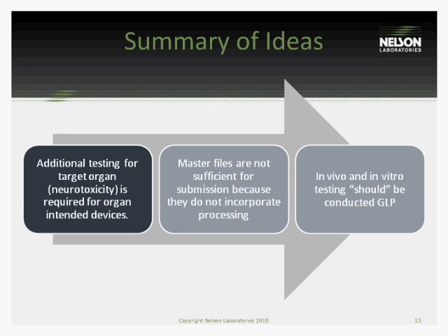Now, master files can help in a risk assessment. In fact, they help a lot in a risk assessment. But you cannot just submit master files and think you have a checkbox with your biocompatibility, because those master files may not have been performed on material that had gone through the same processing as your final device. That's including sterilization. So if your final device is sterile, these master files may have not been tested on a sterile device or a sterile material. So you have to evaluate the impact of your processing to these materials before you can make any kind of risk assessment to get rid of biocompatibility.